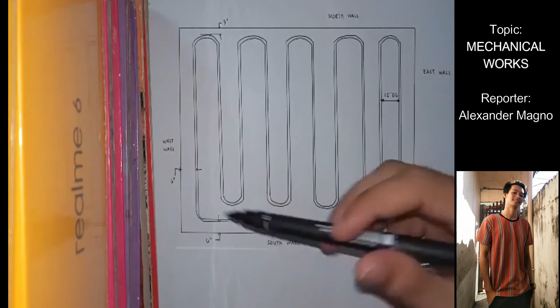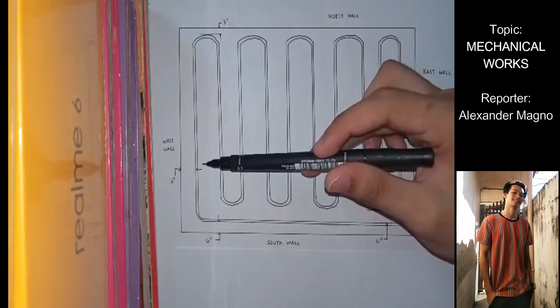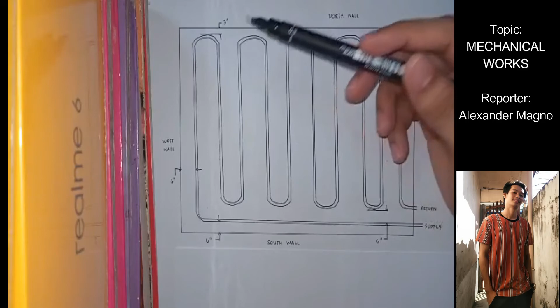So in the given, the spacing between pipes is 12 inch or 1 foot on center. So these are the supply pipes. The distance between the supply pipes and the pipe here is 6 inch. The distance between the pipe along the south wall and the south wall is 6 inch, the distance between the pipe along the west wall and the west wall is 6 inch, and here is 3 inch.